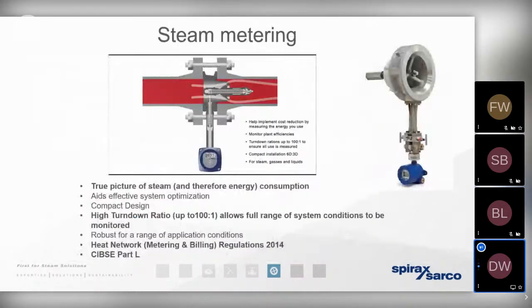So certain applications, especially those where steam is being used for heating or domestic hot water in a public building, are going to require a flow meter to be fitted. So whenever we're performing remedial works, for example, if we're upgrading or stripping down a heat exchanger, then CIBSE Part L states that if we're going to be servicing an elderly shell and tube heat exchanger or a calorifier, then we should be fitting a steam meter in order to remain compliant.